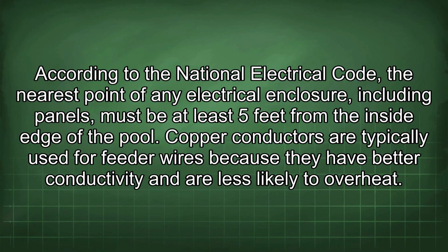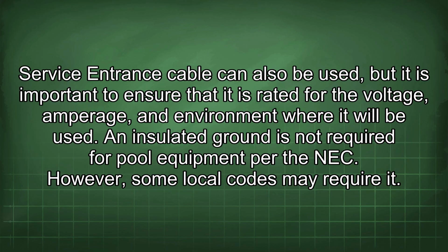According to the National Electrical Code, the nearest point of any electrical enclosure, including panels, must be at least 5 feet from the inside edge of the pool. Copper conductors are typically used for feeder wires because they have better conductivity and are less likely to overheat. Service entrance cable can also be used, but it is important to ensure that it is rated for the voltage, amperage, and environment where it will be used.